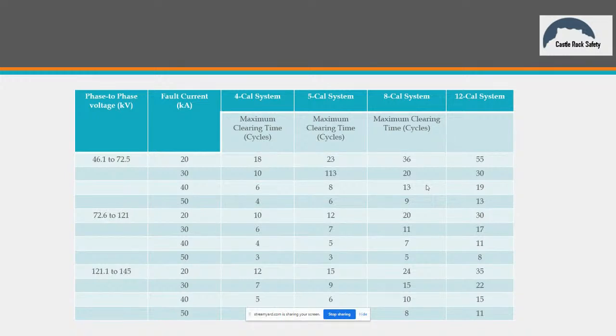The point I'm making here, guys, is that when I'm working up at these higher T-lines, when I'm on a T-line and I'm working on a stick, I'm typically going to be way outside that minimum approach distance. Right. And then I'm going to subtract 2 times the arcing distance from that number. So I guess the point I'm trying to make here, guys, is that arc flash on the utility side is really much less of a risk than it is on the supply side, or I'm sorry, the utilization side. The utility side is less because of the distances and the open air, and there are just a lot of different things that make it not as hazardous.